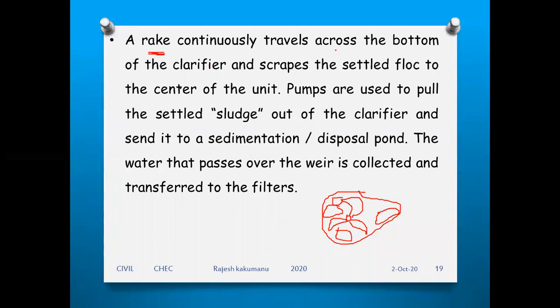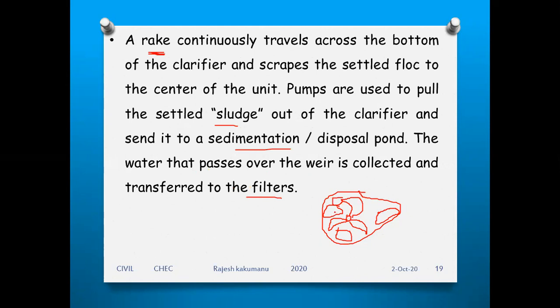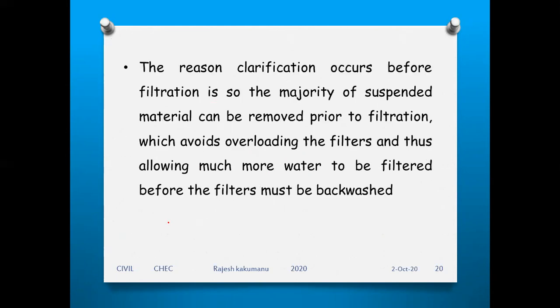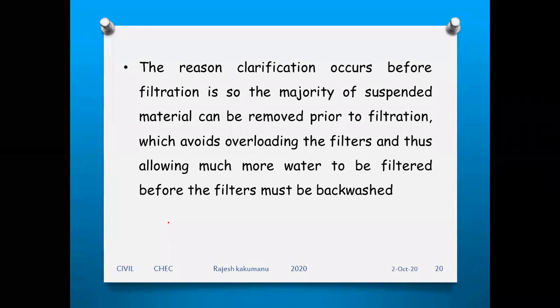A rake continuously travels across the bottom of the clarifier and scrapes the settled floc to the center of the unit. Pumps are used to pull the settled sludge out of the clarifier and send it to the sedimentation or disposal pond. The water that passes over the weir is collected and transferred to the filters. Clarification occurs before filtration so the majority of suspended materials can be removed prior to filtration, avoiding overloading of the filters.